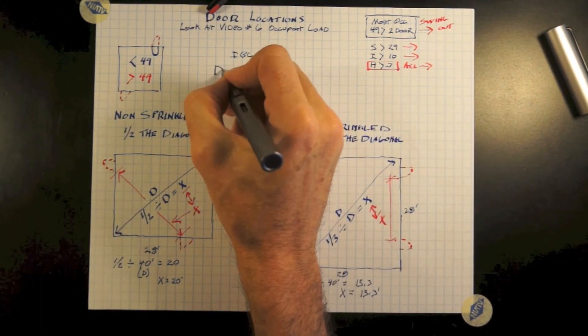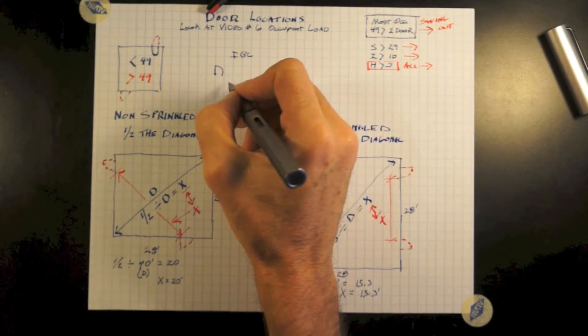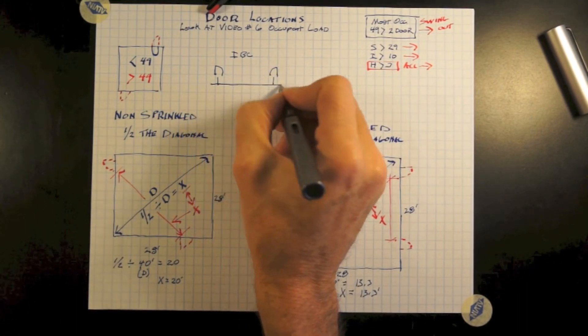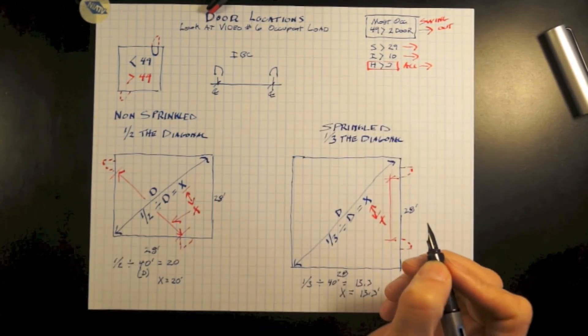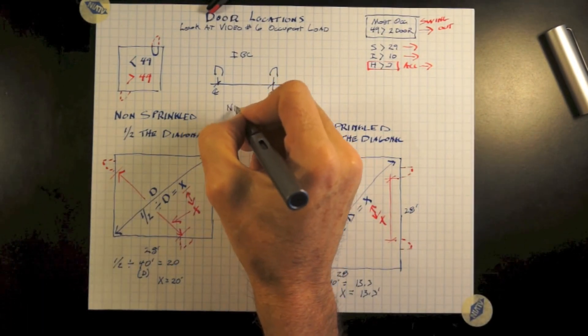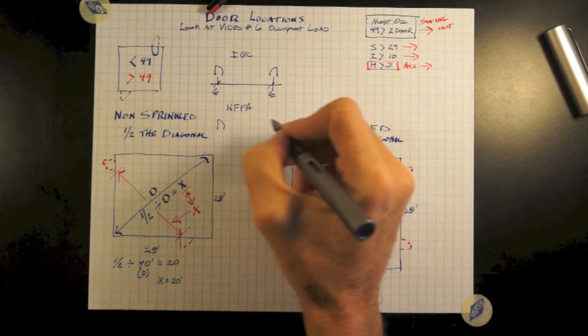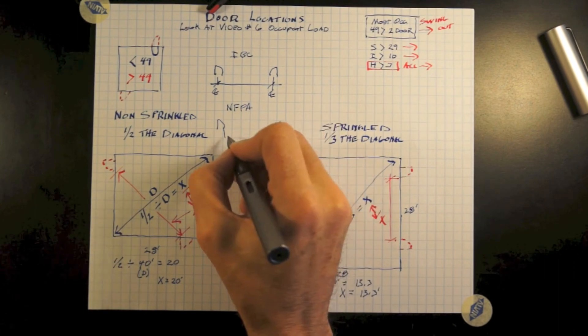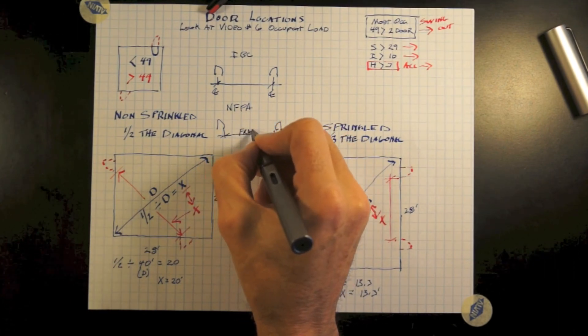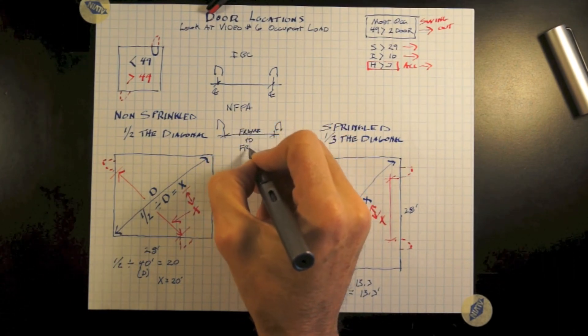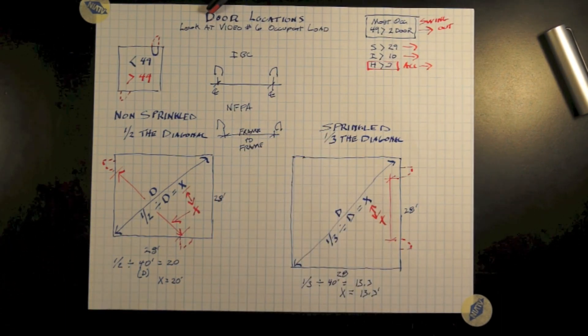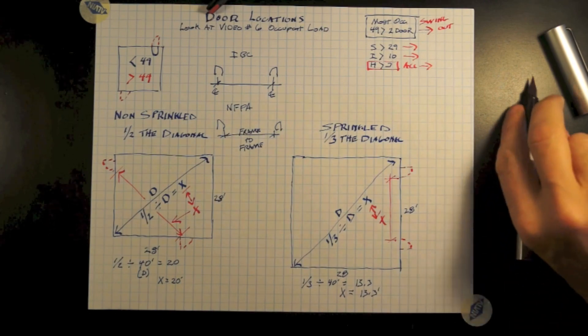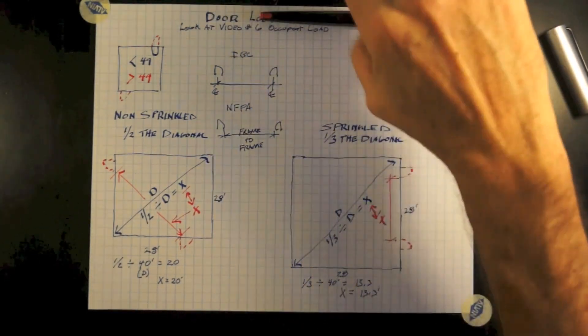One point of note here, IBC considers the definition or the distance between doors is measured from center line of door to center line of door. NFPA measures from door frame to door frame, whichever is closest. So if you're needing to comply with both building codes, you will need to apply the most stringent of the two, which is most likely NFPA.